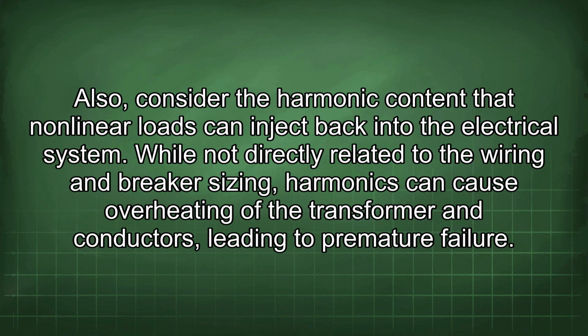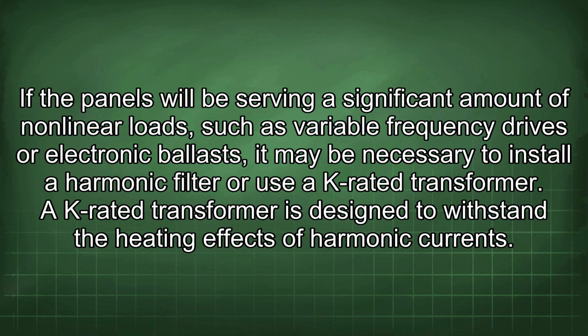Also, consider the harmonic content that nonlinear loads can inject back into the electrical system. While not directly related to the wiring and breaker sizing, harmonics can cause overheating of the transformer and conductors, leading to premature failure. If the panels will be serving a significant amount of nonlinear loads, such as variable frequency drives or electronic ballasts, it may be necessary to install a harmonic filter or use a K-rated transformer.